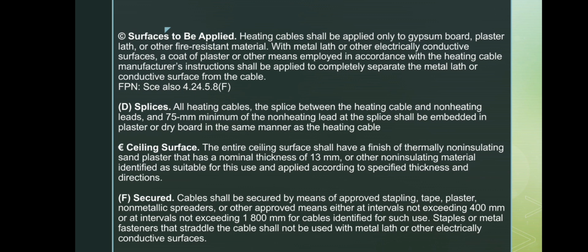Next slide. The heating cable must be installed only on a fire-resistant surface like gypsum board or plaster lath. If the surface is metal or conductive, it must be fully separated from the cable using plaster or other approved insulating material. All splices, along with at least 75 mm of the non-heating lead, must be completely embedded in plaster or dry board just like the cable itself. The entire ceiling must be finished with a 13 mm layer of sand plaster or another approved non-insulating finish.